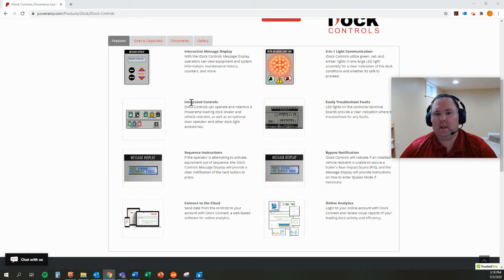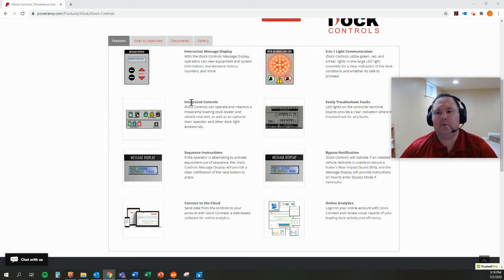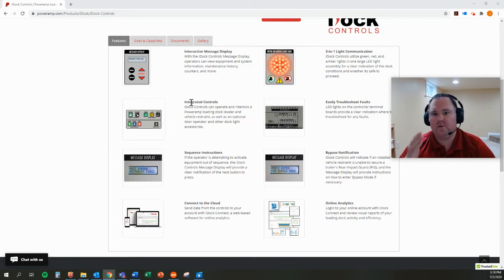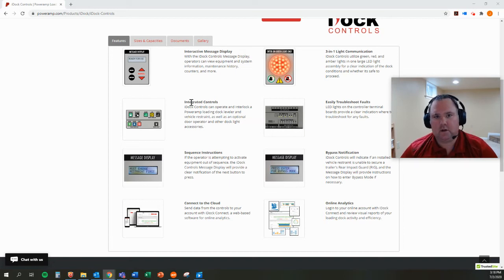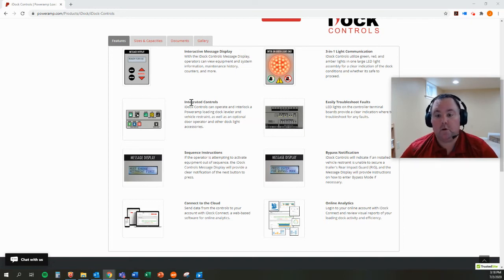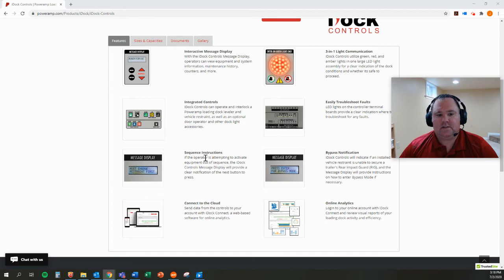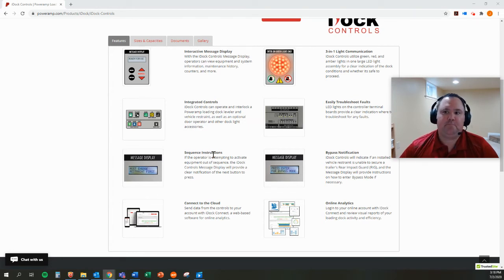And we can interlock the operation of all those pieces of equipment together so that we can require things like the door open is the first step, and then the restraint must be engaged, and then finally the dock leveler can be deployed and it won't work out of order. And that's down here to sequence instructions. That's the next step.